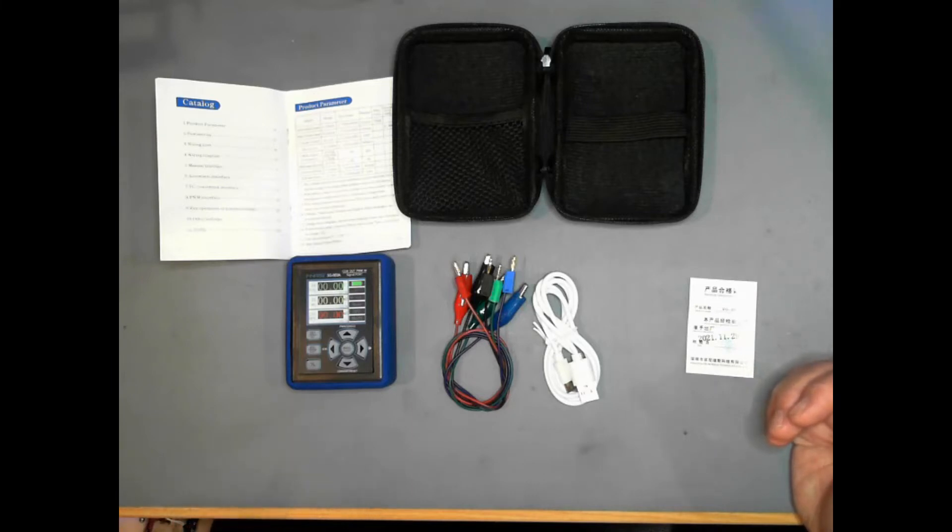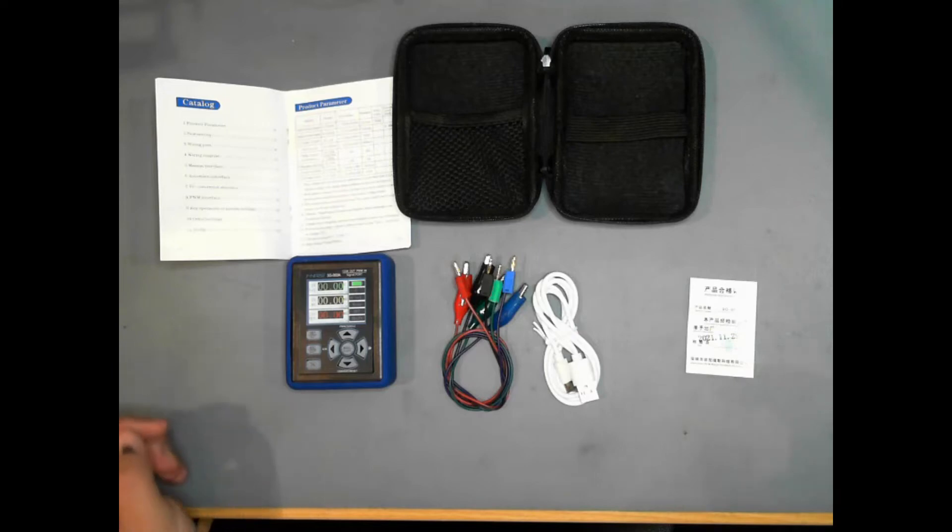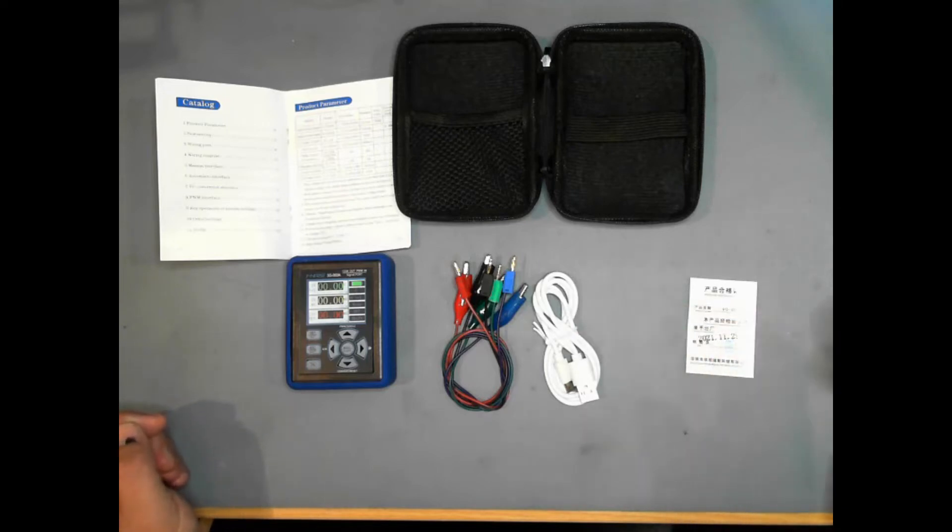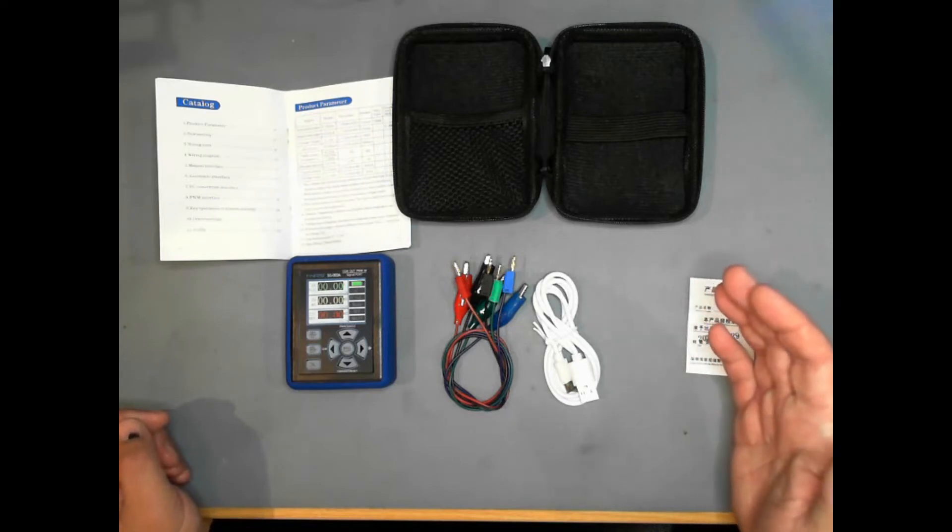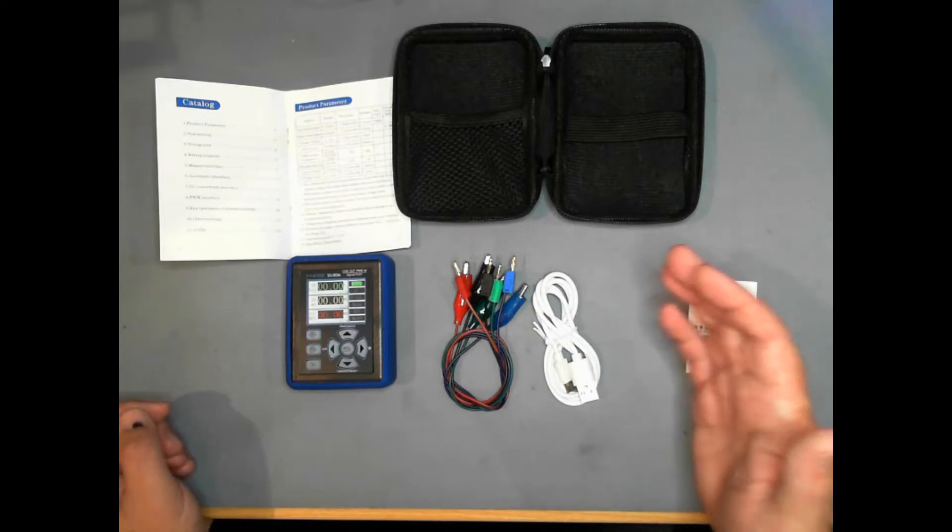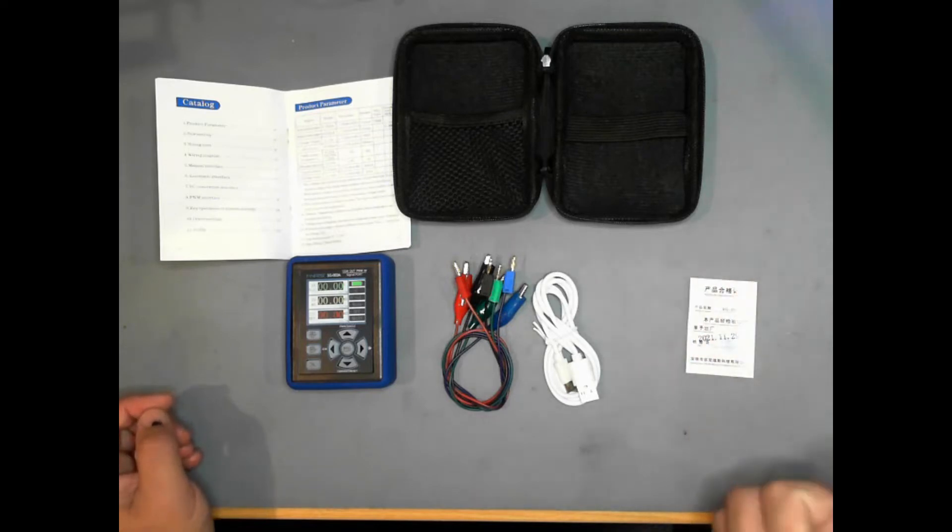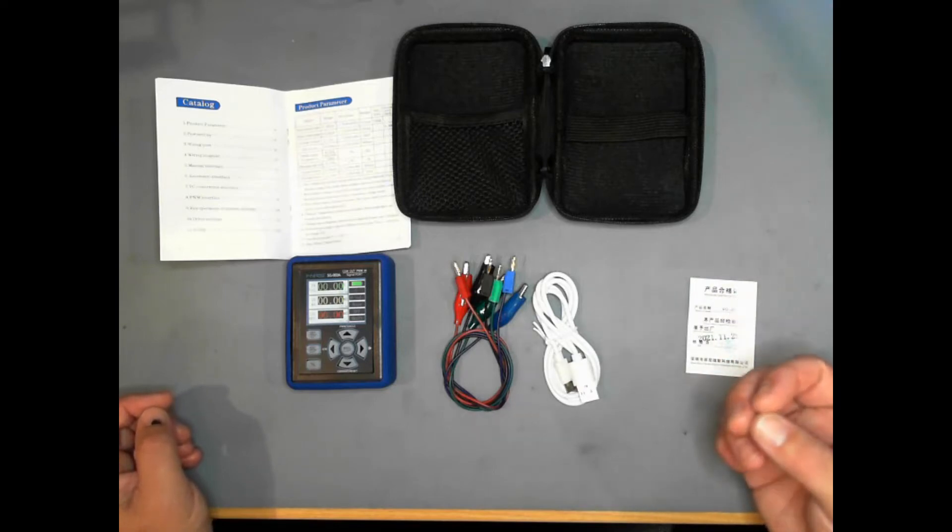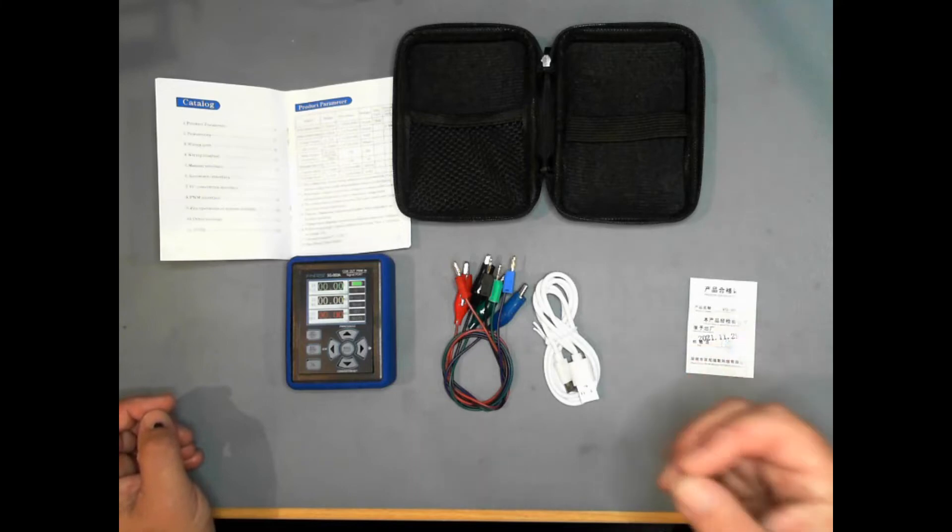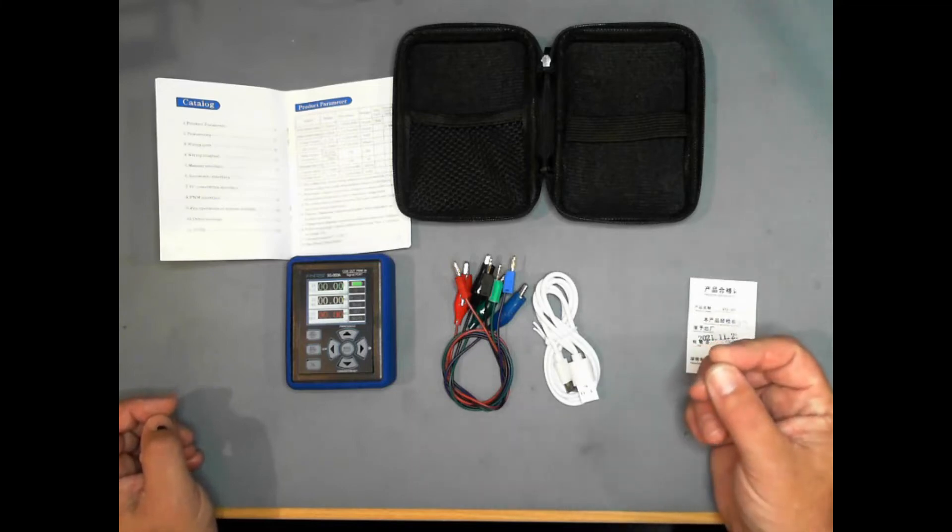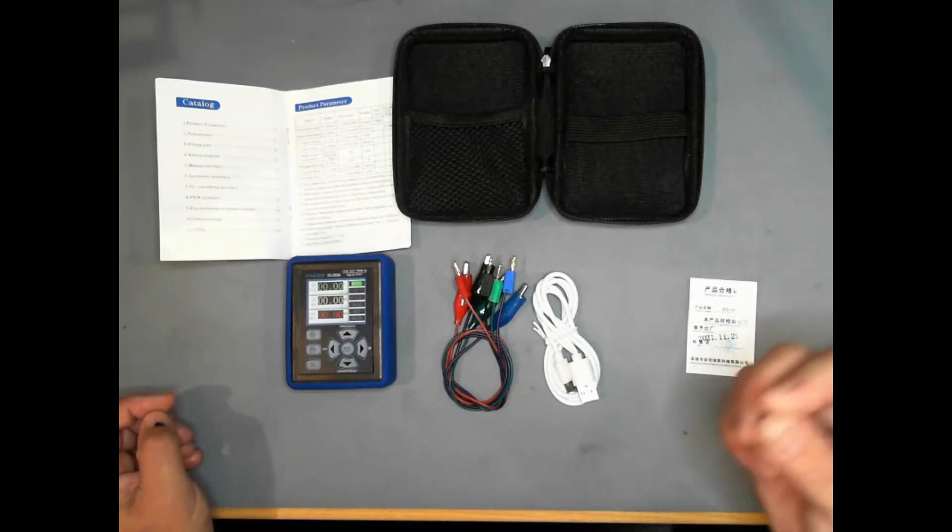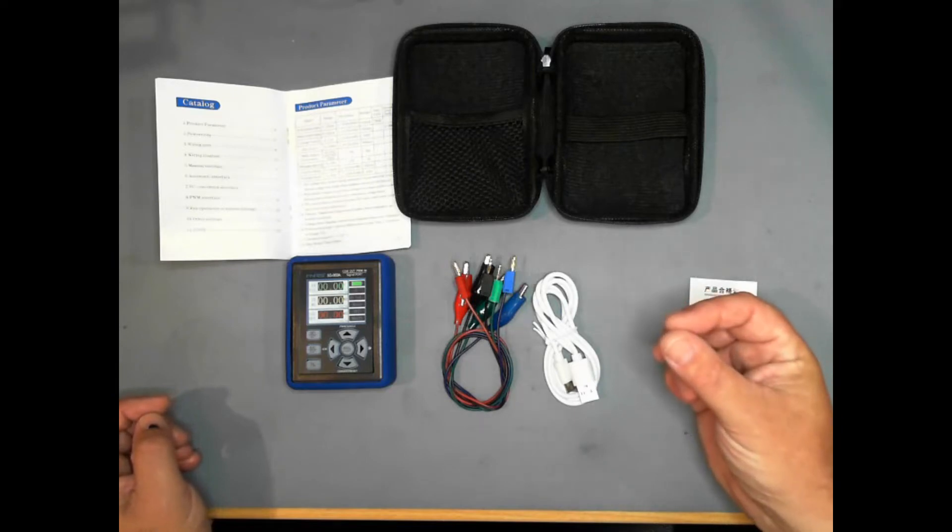You can get very accurate readings from those because it's a current we're reading and not a voltage. It tends to be more immune to electromagnetic interference being introduced into the wires. An electromagnetic interference spike, whether that be RF, inductive or capacitive, tends to affect both wires the same way. In this case the current is flowing in one direction in one wire and in the opposite direction in the other, and so the interference tends to cancel out.